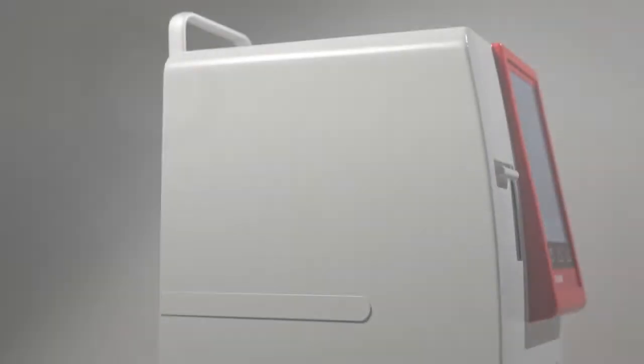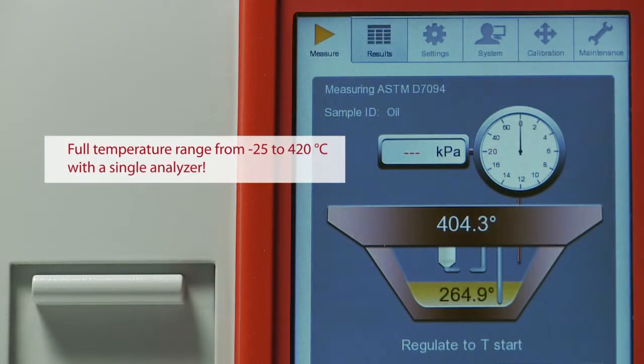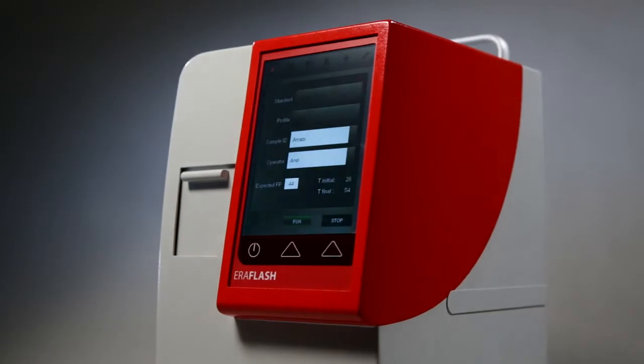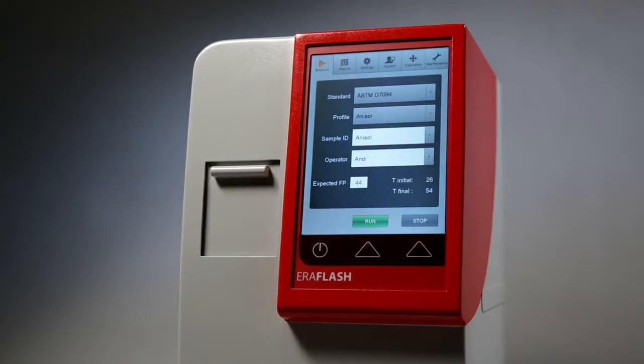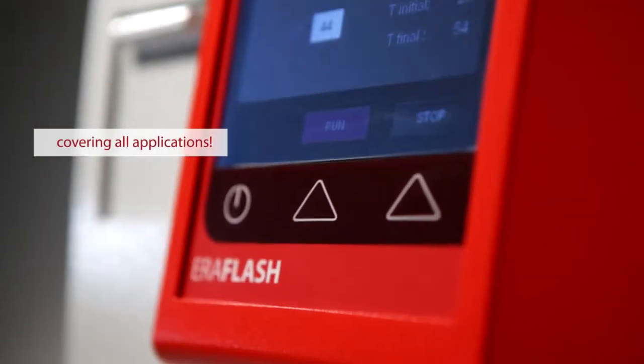Additionally, the unique PBT design makes Eraflash the first and only flashpoint tester on the market to cover the full temperature range of minus 25 to 420 degrees Celsius with a single analyzer. Combined with the typically small footprint and rugged aluminum design of an Eralytics analyzer, Eraflash is the ideal instrument for all kinds of flashpoint testing applications.